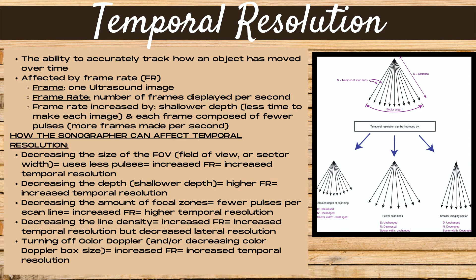Decreasing depth results in a higher frame rate and increased temporal resolution. Decreasing the number of focal zones means fewer pulses per scan line, which increases frame rate and results in higher temporal resolution. Decreasing the line density also increases frame rate and temporal resolution, though note this also decreases lateral resolution. Turning off color Doppler or decreasing the color Doppler box size also results in increased frame rate and increased temporal resolution.